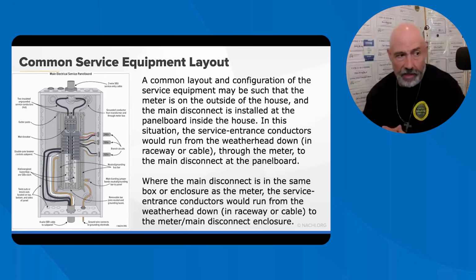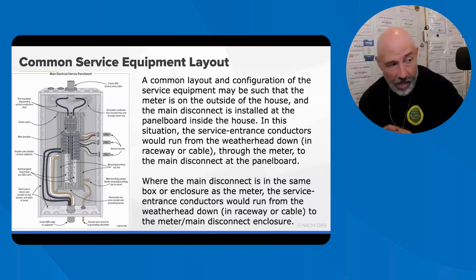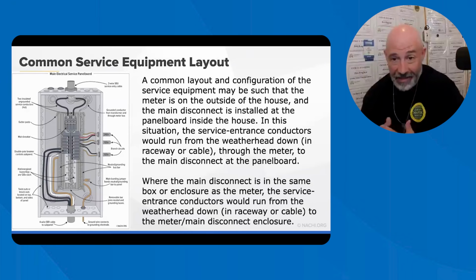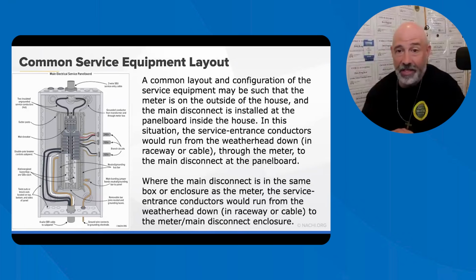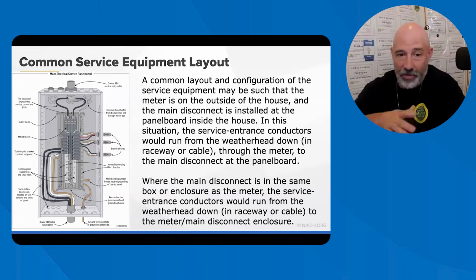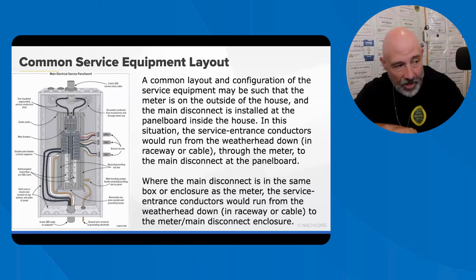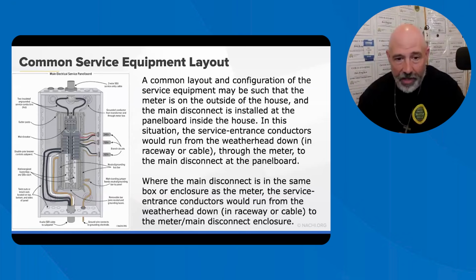So, here is a common layout for the configuration of how the electrical system is laid out. A three-wire SE service entrance cable runs from the meter outside the house into the main electrical panel board, and the panel board contains the branch circuits. In this common installation, the neutral wires, the white, should not touch the grounds, the green or the bare. Take a look at this illustration, take a screenshot of it so that you can get the proper terminology of it. And I'm not going to go through all that.